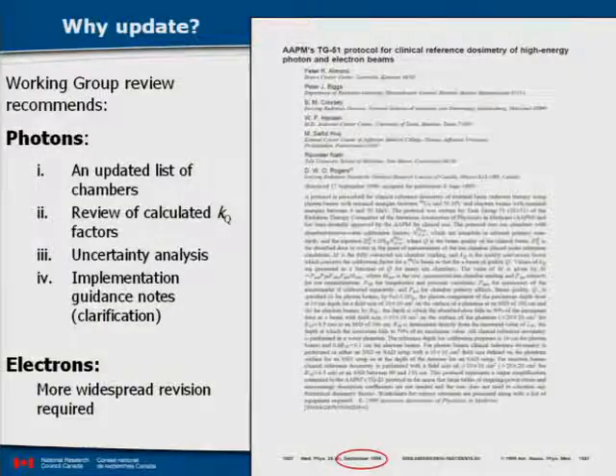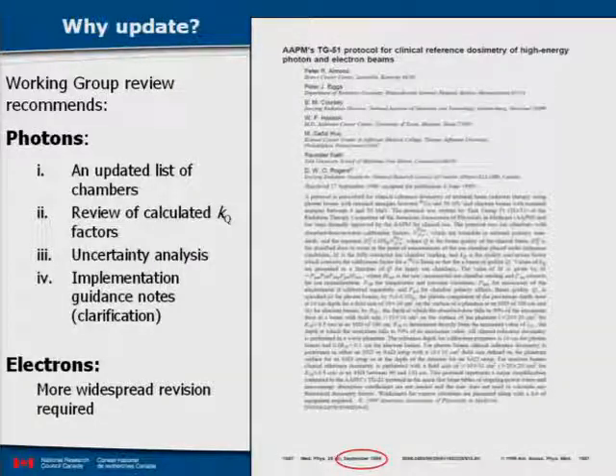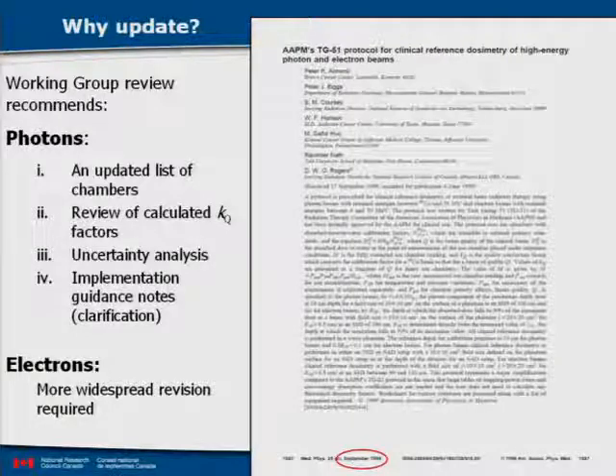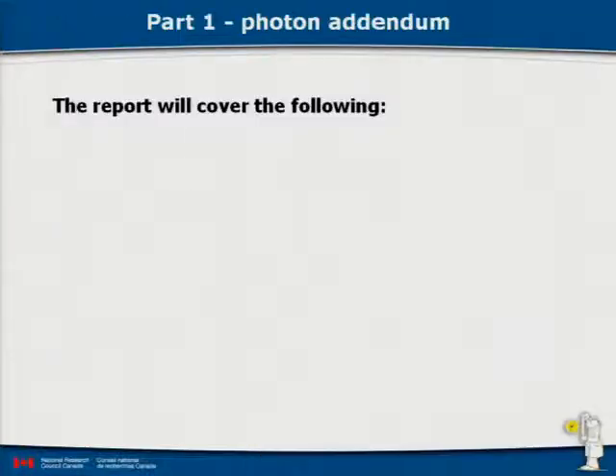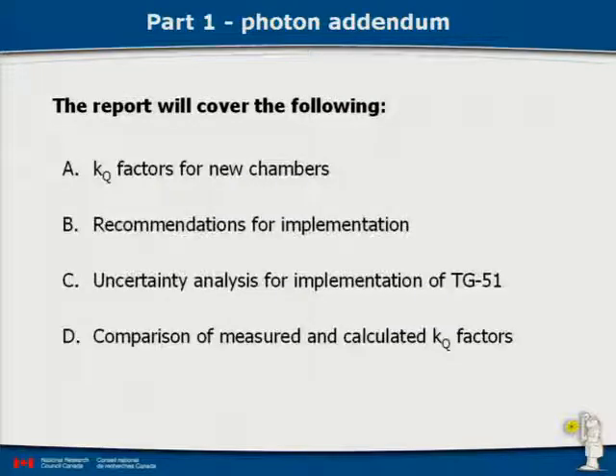For electrons, a more widespread revision is required. Dave alluded to that with one plot where the P wall is very different from the assumption of unity in TG51. At the end of this talk, I'll briefly discuss electron progress and where we need to go. The photon addendum is coming and will cover: KQ factors for new chambers calculated with Monte Carlo, recommendations for implementation, uncertainty analysis, and a comparison of measured and calculated KQ factors.